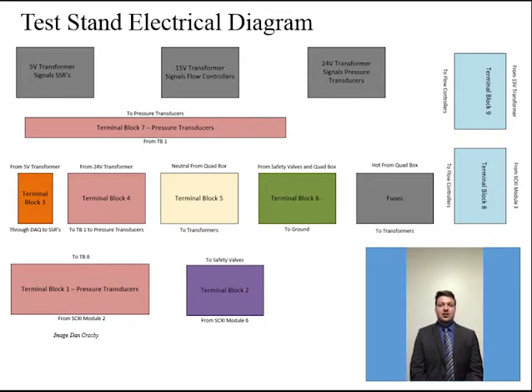The first transformer converts the voltage from 120 volts AC into 5 volts AC. The second converts to 15 volts AC, and the third to 24 volts AC. Transformer number 1, the 5 volt AC, sends signals to the solid state relays, which activate the heaters. Transformer number 2, the 15 volt transformer, signals the flow controllers, and transformer number 3, the 24 volt transformer, sends signals to the pressure transducers.